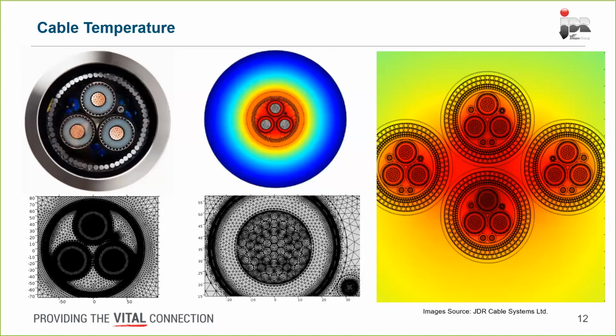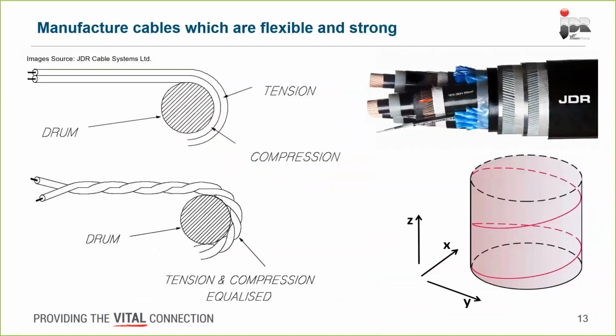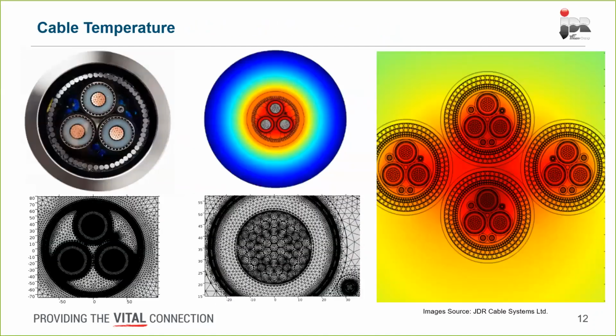That's very similar to when you buy a very long extension cord, like for a caravan, and you're going to draw a lot of power through it for a long period. Most manufacturers say you need to uncoil or unravel that cable to ensure this kind of heating effect doesn't occur. There have been several incidents where that hasn't happened, resulting in fires. So that's something to be aware of when dealing with any electrical cable, to manage the heat dissipation.